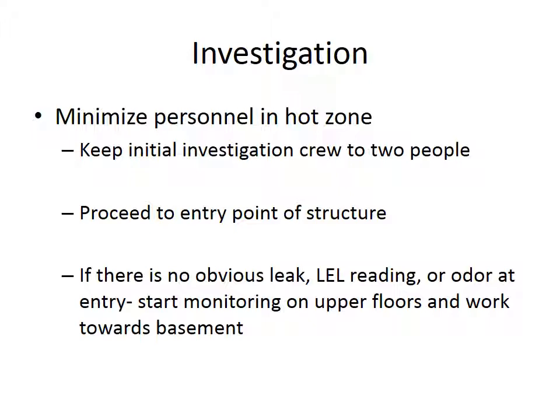Natural gas rises. Unless you get there and you have the homeowner or someone obviously indicating to you an obvious problem that you can go and work to rectify, be worried about monitoring up high. That incident in Prince George's County, what they had there was an accumulation of combustible gas in the void spaces. So that tells me the building probably had a drop ceiling with a void space between the drop ceiling and the bottom side of the roof deck. So they were getting natural gas accumulation in that area. That's obviously something you want to think about. Those areas where natural gas can be getting up and accumulating, get those areas checked.